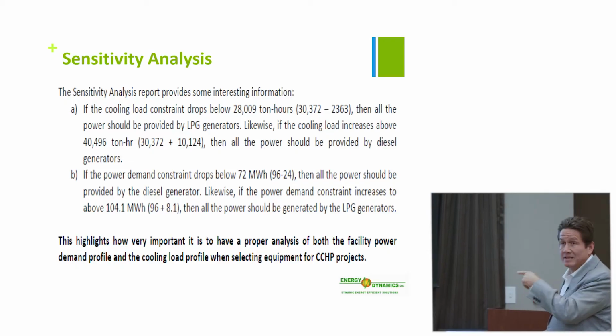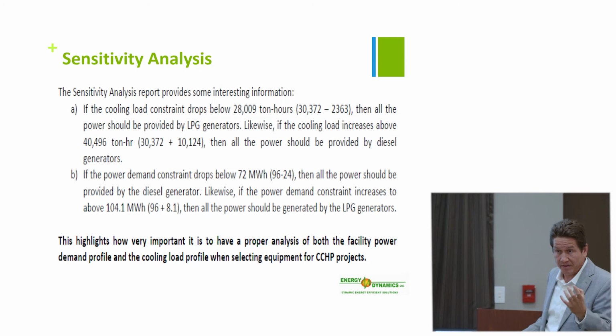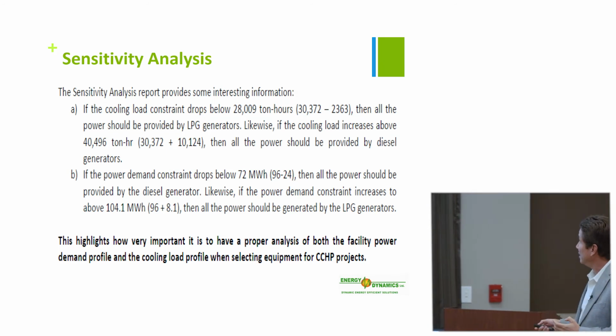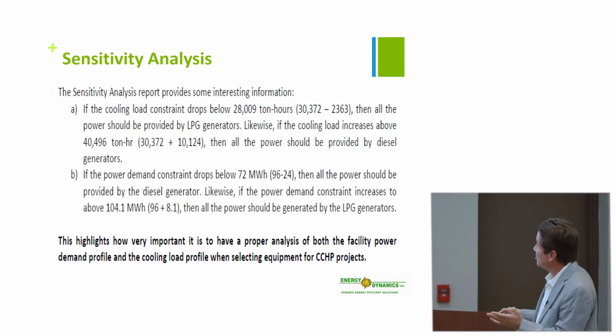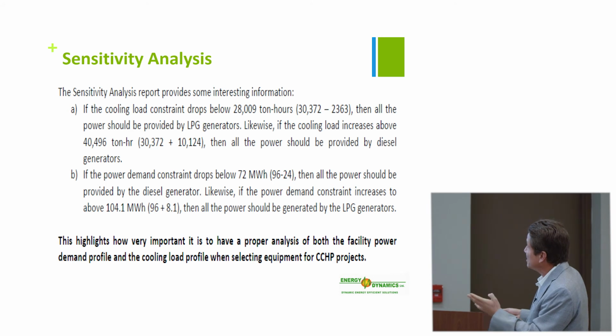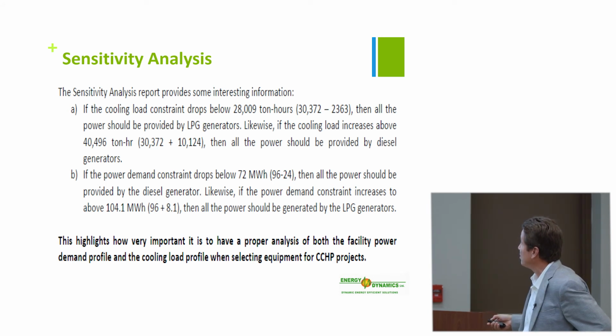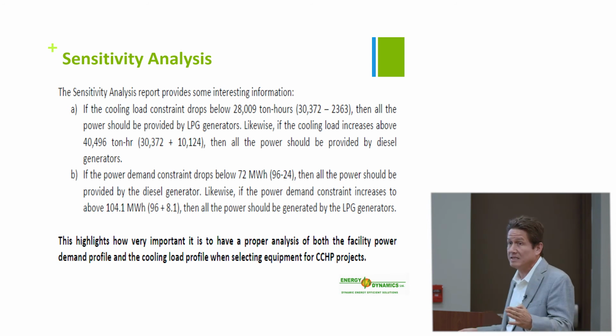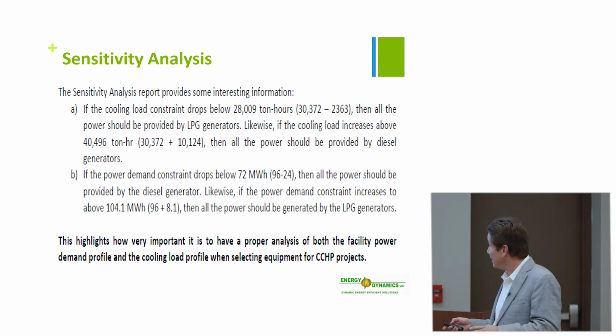So you have to have your numbers properly to get a proper sensitivity, to get a proper end result for the project, for the customer, okay? And the other one - if the power demand constraint drops below 70 megawatt hours, then all power should be provided by diesel, blah blah blah. This highlights how very important it is to have a proper analysis of both the facility power demand profile and the cooling load profile when selecting for CCHP projects. You have to do your analysis. That's clear, all right?